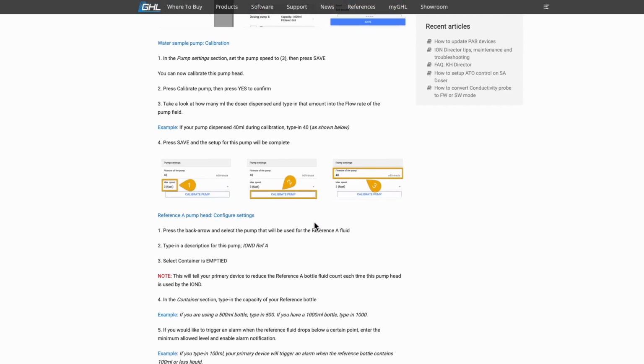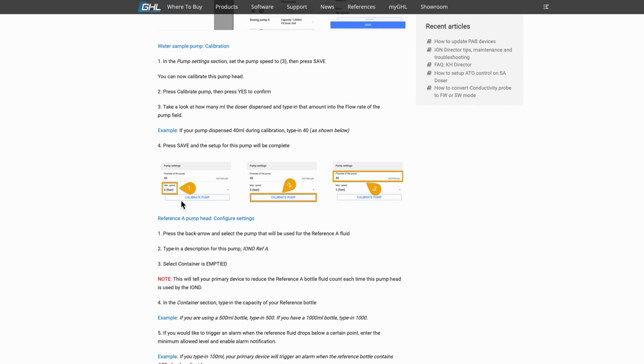It wasn't too bad. You've got to do that with each of the pumps, so you've got to do that 3 times. It's not too bad with the first one because that is just salt water. So you measure the fluid coming out, and then once you finish, you can just hook that back up to the Ion Director. You're good to go. I did find it a little bit awkward that it tells you to hook up to the Ion Director, and then you've got to disconnect from the Ion Director because you've got to calibrate these pumps. I wish there was a step in there that said, before you hook it up to the Ion Director, let's prime and calibrate this pump. But oh well.